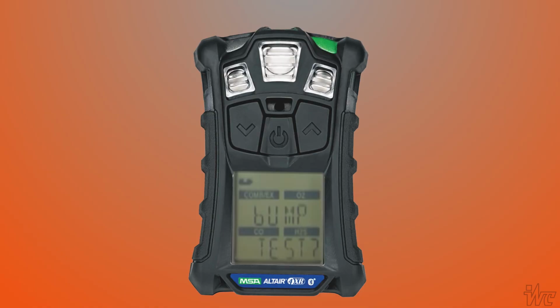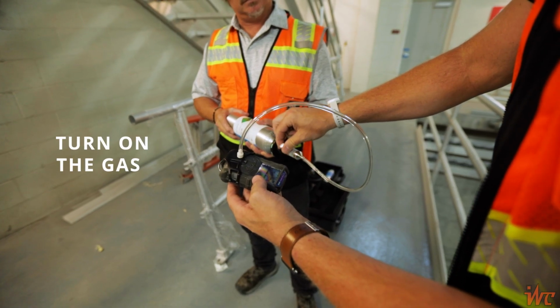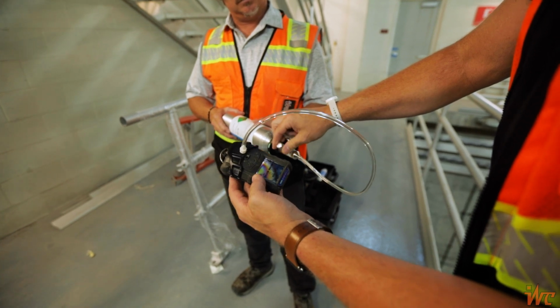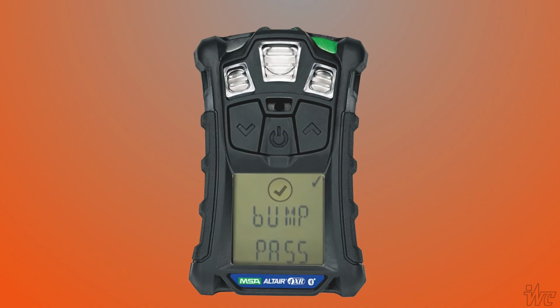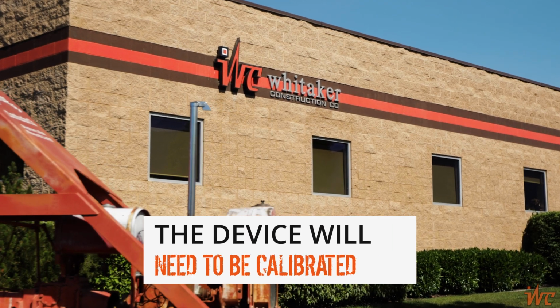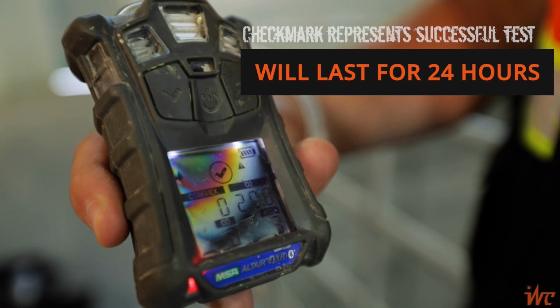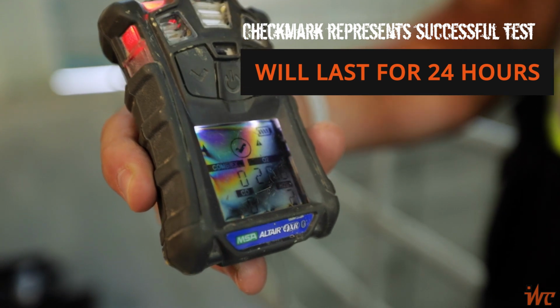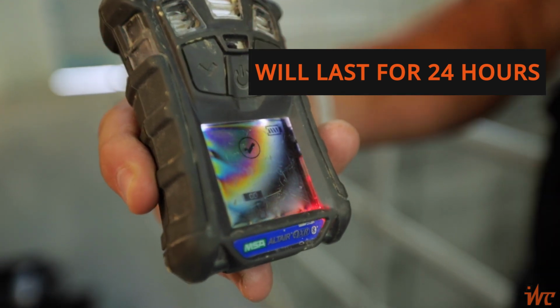Navigate to the bump test menu by pressing the down arrow. Press the enter button to start the bump test and then turn on the gas from the canister. Once this test is completed, you will either get a bump pass with a check mark or a bump error on the notification screen. If the bump error message shows up, the device will need to be calibrated at the Brigham City office. The check mark represents a successful bump test. The check mark will last for 24 hours.